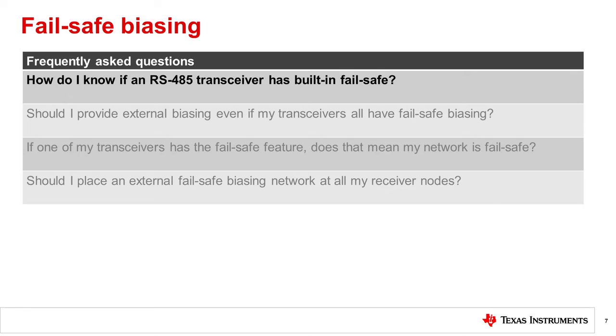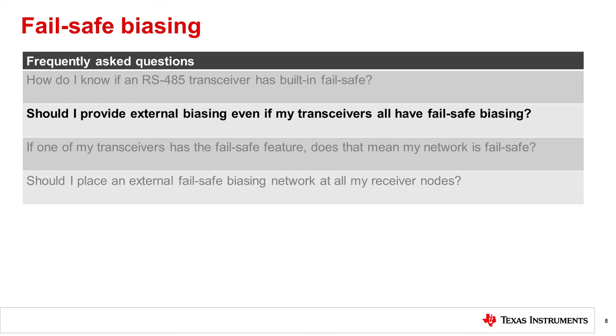A transceiver with fail-safe biasing typically will not center the threshold values around 0 volts; the expected values from fail-safe biasing receivers should be negative values. Note that some newer RS-485 transceivers include circuitry that centers V input thresholds around 0 volts and can still provide fail-safe biasing, though this check method should still work for a majority of RS-485 receivers. External biasing is not necessary if all transceivers have built-in fail-safe, since they should still hold RX in a logic high state in the event of a short, idle, or open condition on the transmission line.